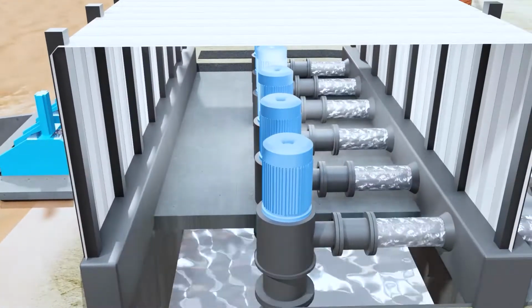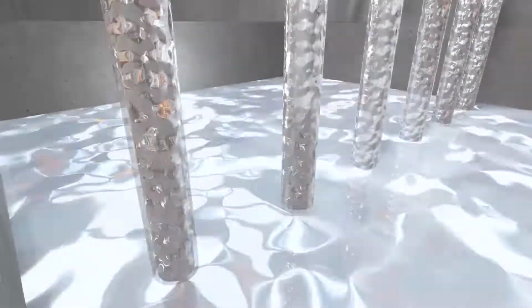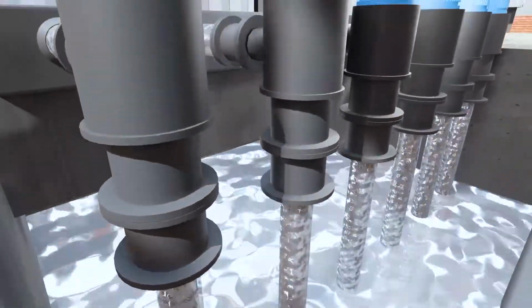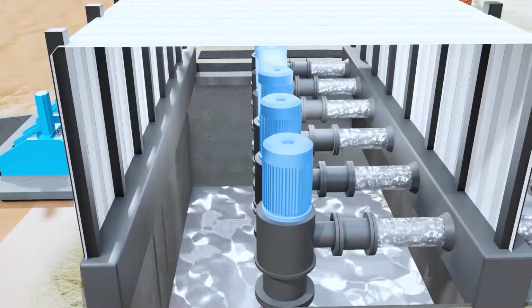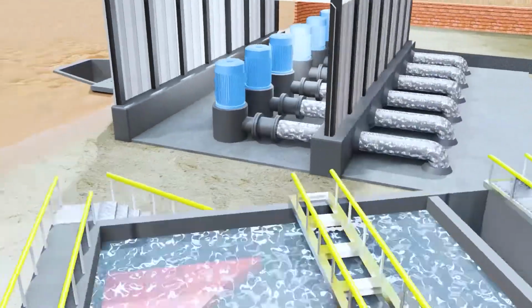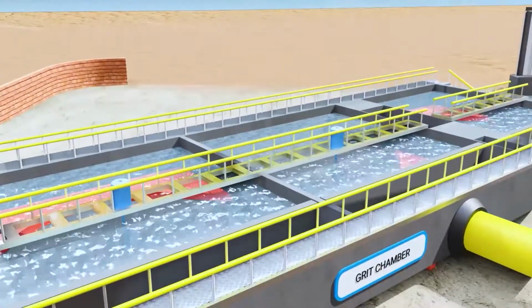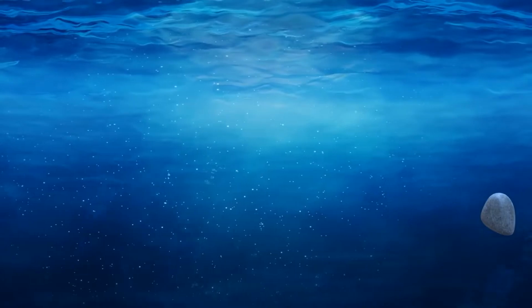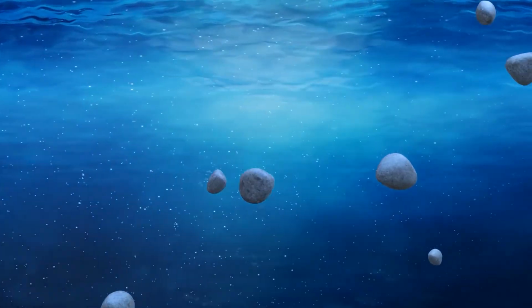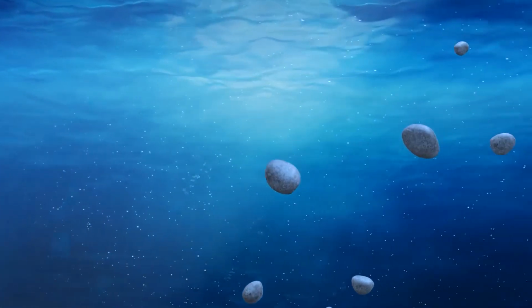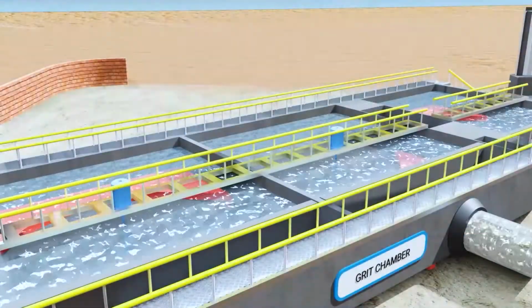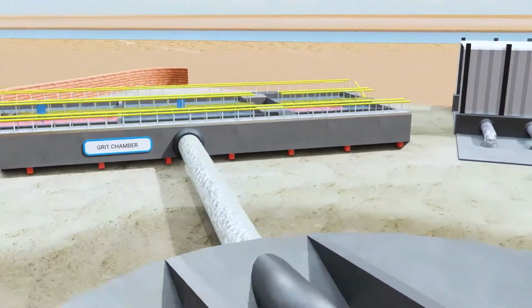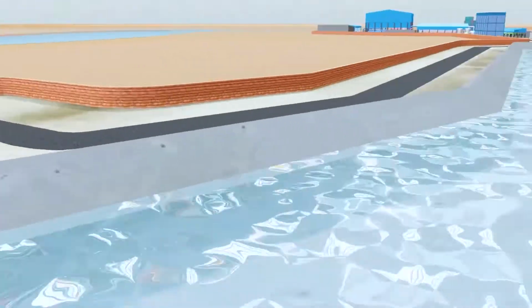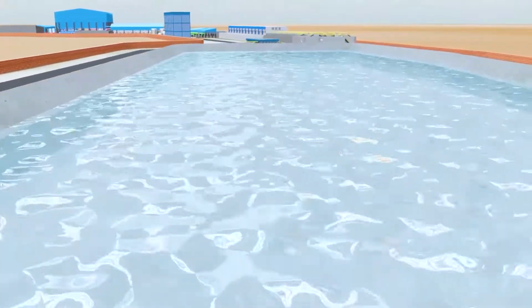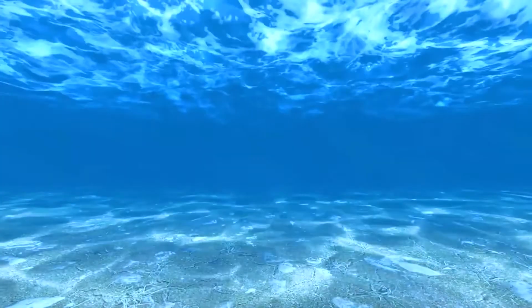With the help of vertical turbine pumps, water will be pumped out from the pump house to the grit chamber. The function of a grit chamber is to slow down the flow of water so that relatively heavier particles like pebbles, stones will be separated from the water flow. From the grit chamber, water will move to the reservoir through the pipeline by means of gravity, where water will be stored for a day for natural sedimentation.